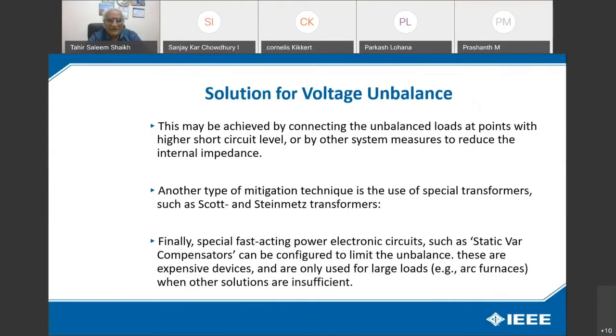This may be achieved by connecting the unbalanced loads at a point with higher short circuit level or by other system measures to reduce the internal impedance. Another type of mitigation technique is the use of special transformers, such as Scott and Steinmetz transformers. Finally, special fast-acting power electronic circuits, such as a static VAR compensator, can be configured to limit the unbalance. These are expensive devices and only used for large loads, for example arc furnaces, when other solutions are insufficient. VAR capacitors are used on the transmission lines.